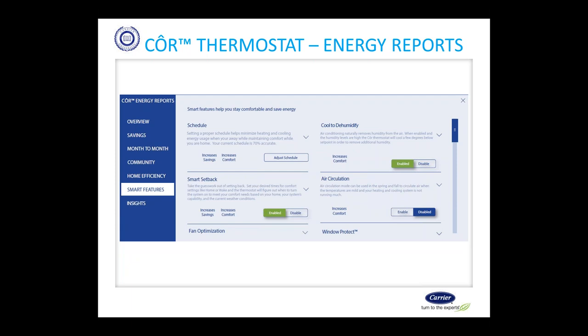And that is true if you have single stage equipment, right? Because you turn it on, it's a certain efficiency and heats back up, great. When you have multi-stage equipment, the game really changes, because running your furnace on stage one versus stage two is not the same efficiency. In one scenario, I have much less gas flow than the other, but I have the exact same heat exchanger surface area. So if I have a two-stage, or even more stages, if you will, but a two-stage furnace, running it on stage one is going to be a higher AFUE running point than it would be running it on stage two. So let's just say, for sake of argument, it's 95% efficient when I run it on stage two, but it's 97% efficient when I run it on stage one. I know it's 2%, it's not a big deal, but it matters over the course of a year or 2 years or 3 years. It adds up to real dollars.